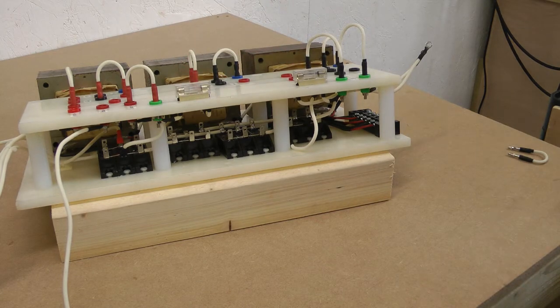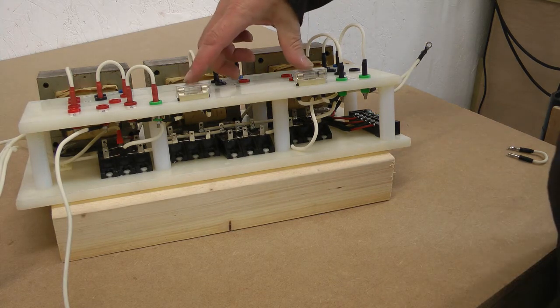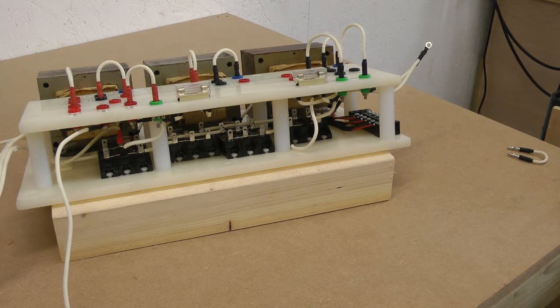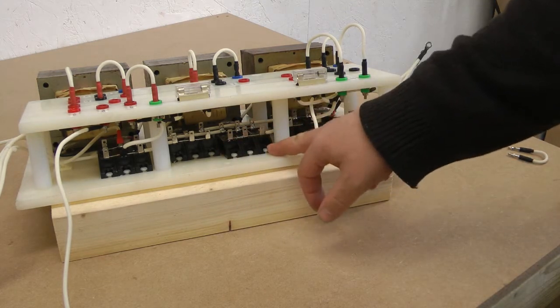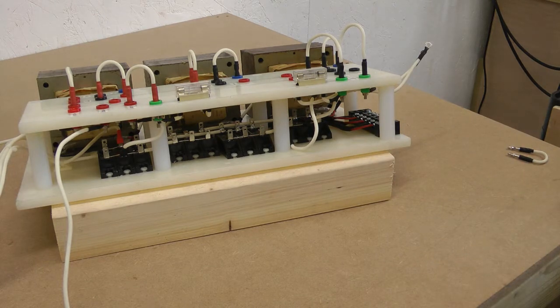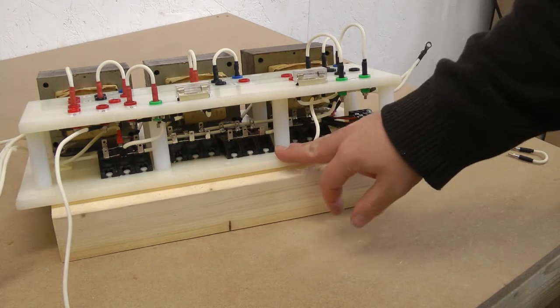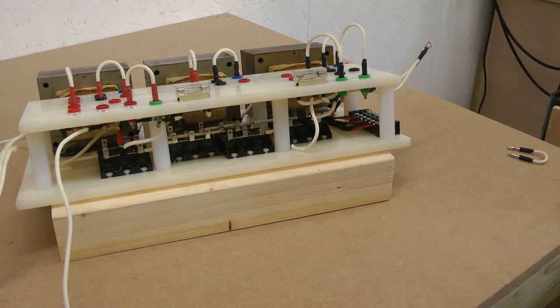So I put the fuses in. That stops that condition quite adequately. I would run those with a 2 amp quick blow, which is enough. You can run it continuously between 2 and 3, and it's still going to be okay. But once you get up a little bit higher than that, the fuses blow quite quickly, which is good. It protects. Since each arm is 6 amps rated, it's adequate to protect the semiconductors there, and I've not had a problem with it since. Again, that's all mounted down on nylon screws. It's all wired up underneath using the same 20 kilovolt silicone wire.